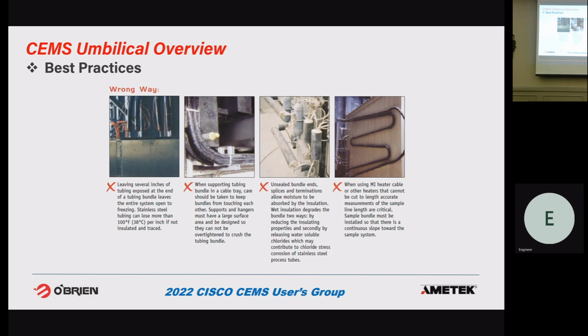This last one here is a great example of why I don't think MI tracer is a great fit for tubing bundle. As I said, MI tracer, you cannot cut to length. You buy a specific length, you buy a 150 footer, we put it in a tubing bundle, you get a 150 footer, and you've got to make do. So they had extra bundle, they ordered too much. And so this is their shelter. It came down from the stack, they ran it down here and back up. The biggest problem with this is that you've got this low point right here. If they would have just wrapped it around the shelter in a slow descending order and then gone into the shelter, it would have been fine.